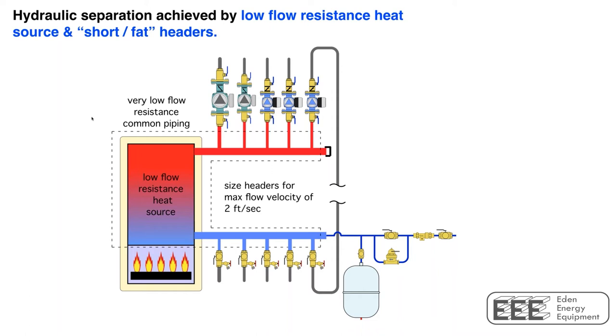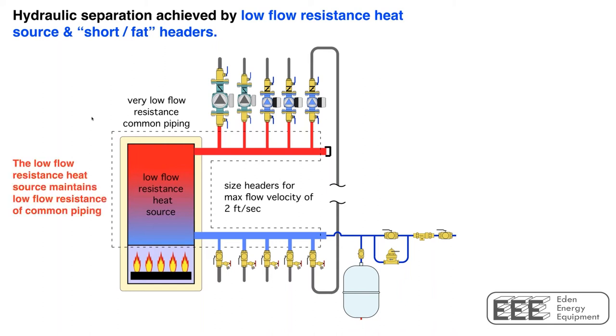Looking at this schematic generically — yes, that could be a cast iron sectional boiler, but it could also be a tank heated by a heat pump, with the heat pump built right into the appliance along with the tank. There are several products now in the European market that combine the hardware of a heat pump — whether water-to-water or air-to-water — with a buffer tank, all the valving and controls built together. One of the key hydraulic details is that there's very little pumping power required to move water through that heat source, so that combination becomes the hydraulic separator in combination with low loss headers.